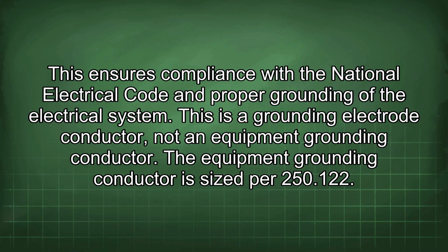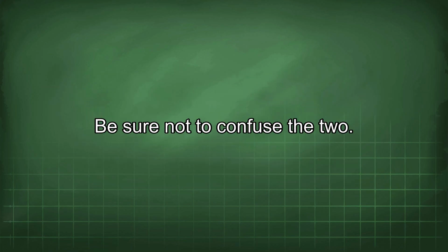This is a grounding electrode conductor, not an equipment grounding conductor. The equipment grounding conductor is sized per 250.122. Be sure not to confuse the two.